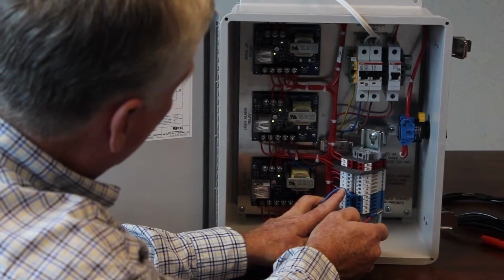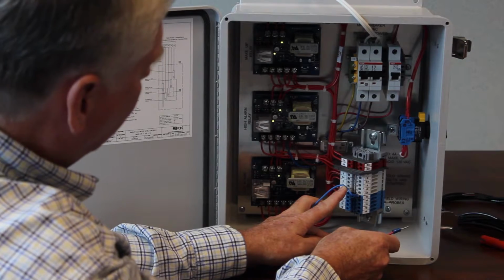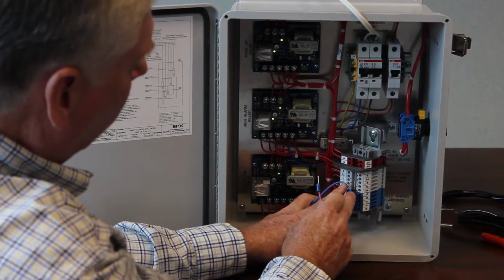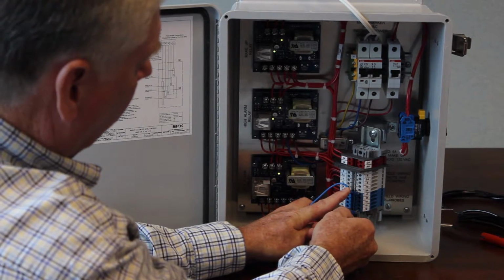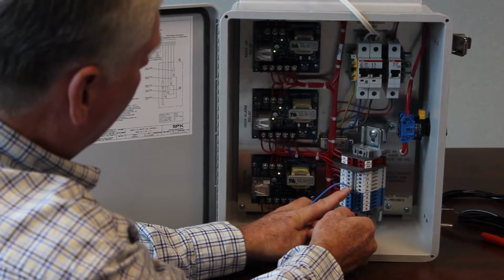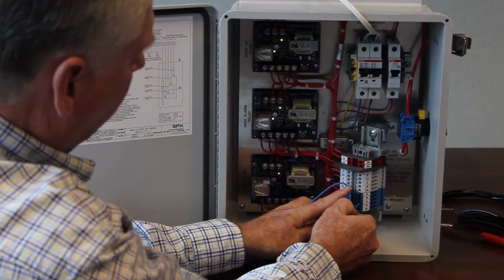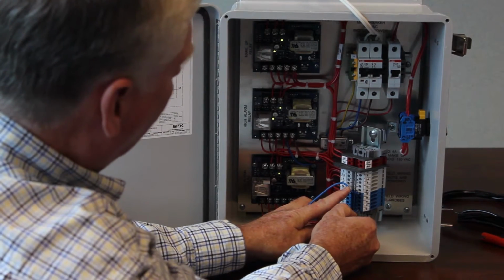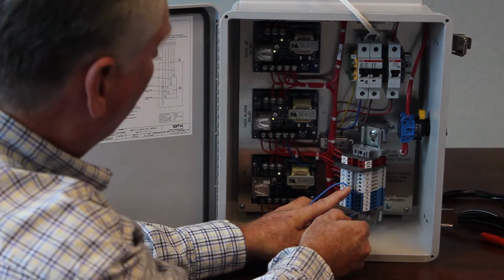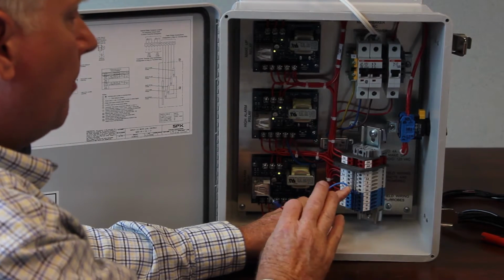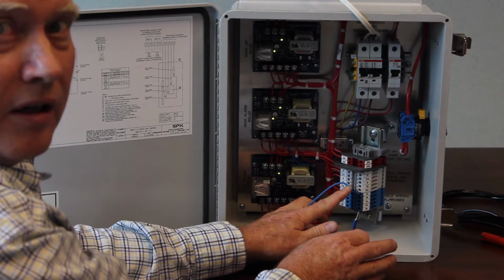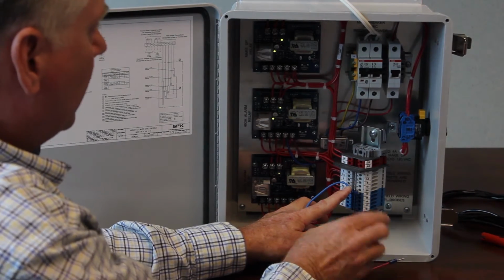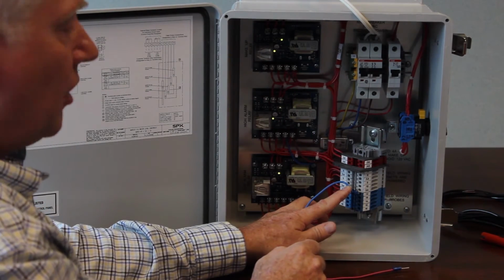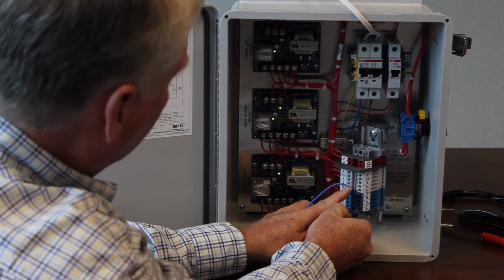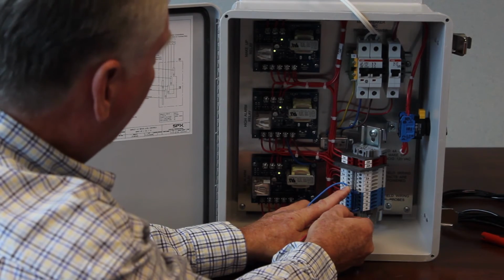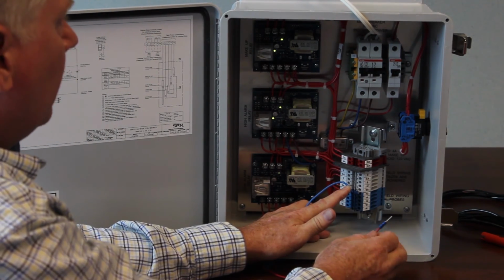So let's go to the next card, which is your high alarm card. I believe that's probe number 16. We're just going to repeat the same process. Keep your wire on number 13, which is the reference probe. It's always in the water. I'm going to attach this to number 16. Now you see the relay on the high level relay card here in the middle change state, and you can see the light come on and off. We're going to have a chart in this video that tells you, based on what the probes are seeing, whether the light is going to be on or off on these cards. There are actually 2 different cards in here. Some work in reverse order, so that chart comes in really handy. I'm going to show you this one more time. Number 16, high relay card. It appears to be functioning just fine. So far I feel good that this panel is working. Next we're going to go to the makeup card.